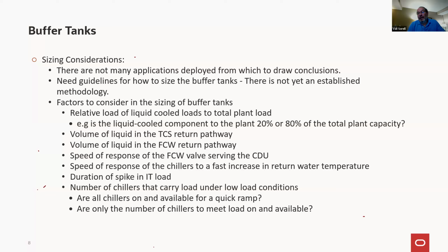The one thing I wanted to point out is that starting from a full load at the IT level, you've got the hottest possible water coming out of it. The plant has no problem with that. It's the rate of change leaving that IT rack that is the issue at the plant. It's the plant being able to keep up with that kind of very steep rise in incoming temperature. Once the chillers are up and running and more or less tracking that load, you can drop your load and pick it up again. Thermal mass just takes care of it. The buffer tank serves no purpose at that level. It's only that rate of change.